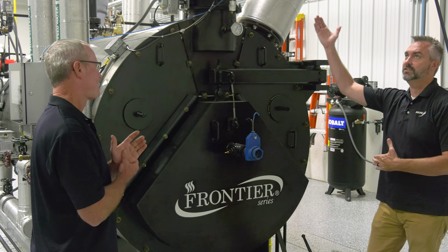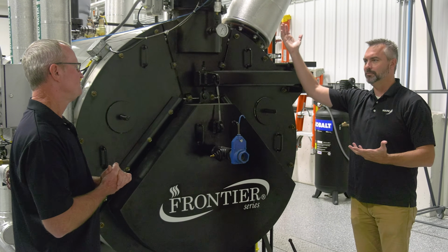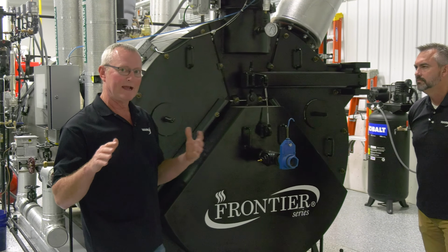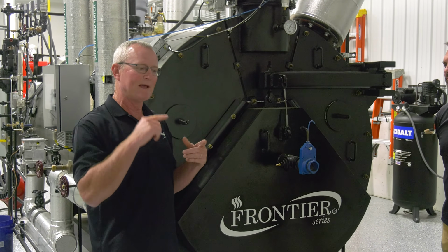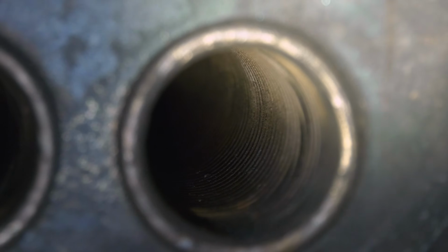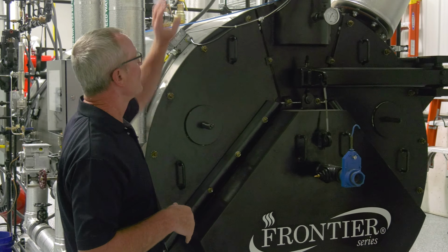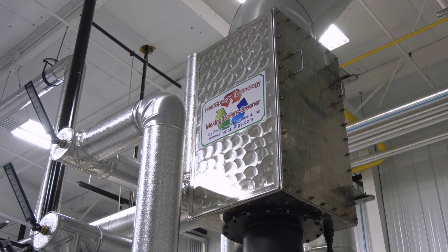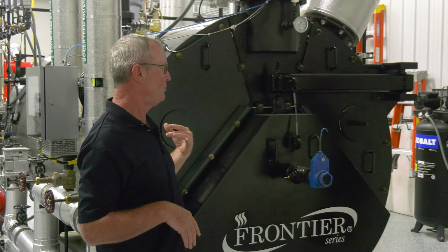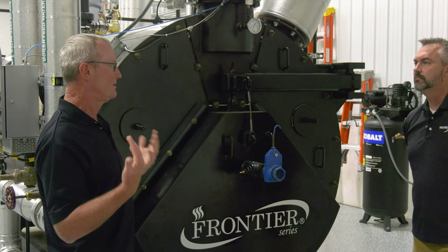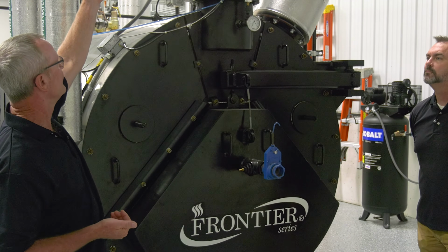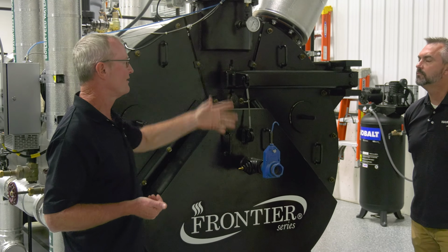What happens with the stack when the temperature's low? What's actually going on? That's the other problem we have to watch with these XID tubes. These XID tubes have got rifling inside the tube, and it gets a lot better heat transfer. We have to watch when we put an economizer on there. If we oversize the economizer, we'll drop the stack temperature below the dew point, which causes it to start to condense. Then we've got water coming down through there. If it's not all stainless steel, this one is. But if it's not, everything starts to rust out.